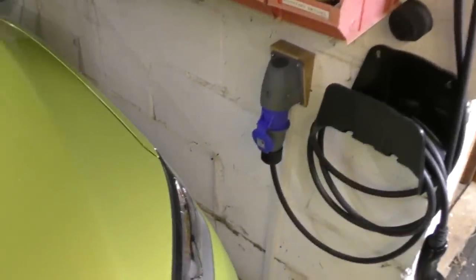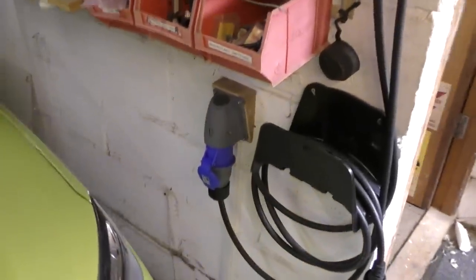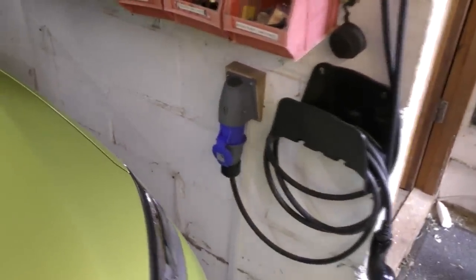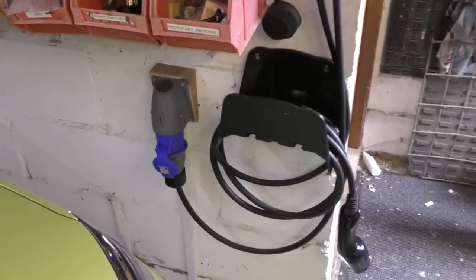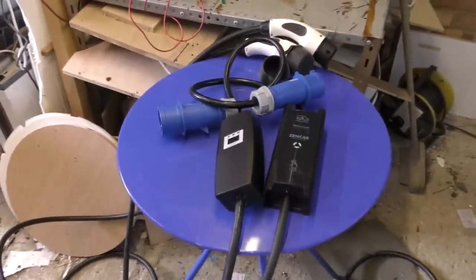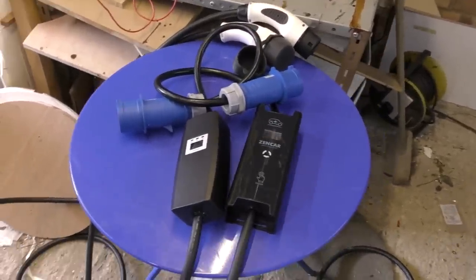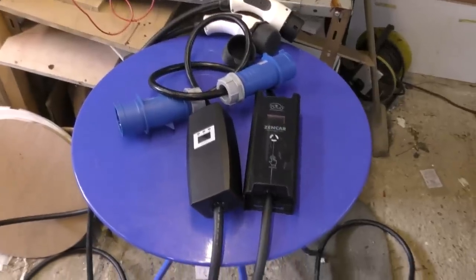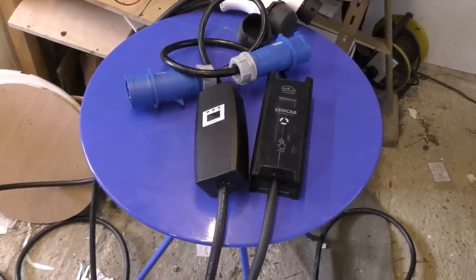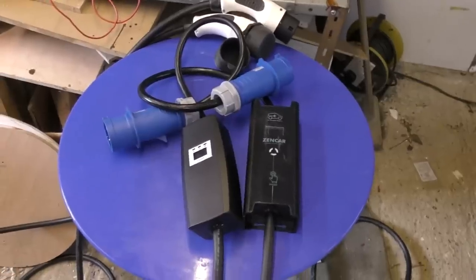Things probably get a little bit more vague if you just install a generic 32-amp outlet. Then there could be arguments made that this is a general purpose socket and not an EV charging socket, so those regulations don't apply, but that's really an administrative argument to have rather than a technical one. Obviously, the chances of having a DC fault are pretty low. And the granny charger, certainly I know the Hyundai granny charger doesn't detect DC faults, because I've actually done some tests to verify that. I suspect these two probably don't either, but we'll do some tests to actually measure the actual residual current performance to see whether they can actually detect that or not. But lack of that, I wouldn't say is a huge issue, because it's a pretty improbable fault situation.